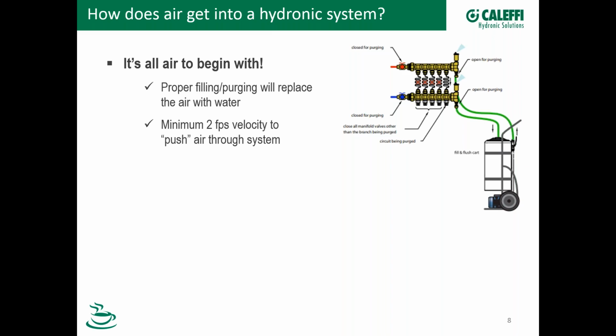It's just perfect. So one thing to remember is you need to have enough of a pump. You need to have a good fill pump and enough velocity to push all the air through the piping as you do the fill. And you need to have at least 2 feet per second. This is a velocity that is sort of the key speed at which an air bubble will be able to be pulled through the piping. For example, in a vertical pipe, if you have 2 feet per second, the air bubbles will be pulled along with the water. If you have less than that, the air bubble buoyancy will actually keep the bubble from being flushed through the piping. So that's something to be concerned with.